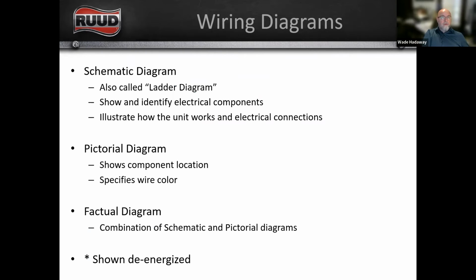So we have really three types of diagrams when we're talking about electrical wiring, and these will be located in the installation manual. They'll be in PTS under wiring diagrams, and they'll also be on the panel somewhere, right? So on an outdoor unit, you pull off the electrical panel, flip it over. Sometimes you'll have a wiring diagram there. There's typically one on the indoor product. Sometimes those diagrams can get damaged, but you can always get them online on PTS or in the installation manual.